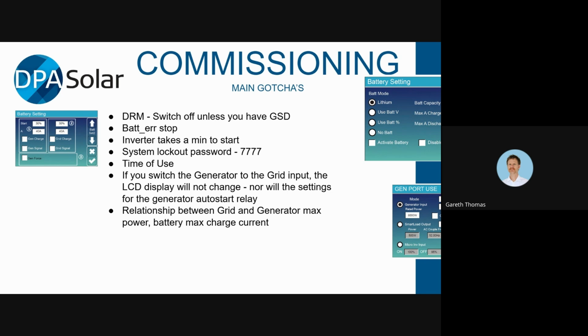If you switch the generator to the grid input, the LCD display will not change, nor will the settings for the generator auto start relay. So you still set the generator auto start relay in the same place. And when you're looking at the power flows on the screen, if you've got the generator on the grid input, it will show power coming in from the grid. And if you've got the generator on the generator input, then it will show it that way, even if you've ticked that box saying that the generator is on the grid input.